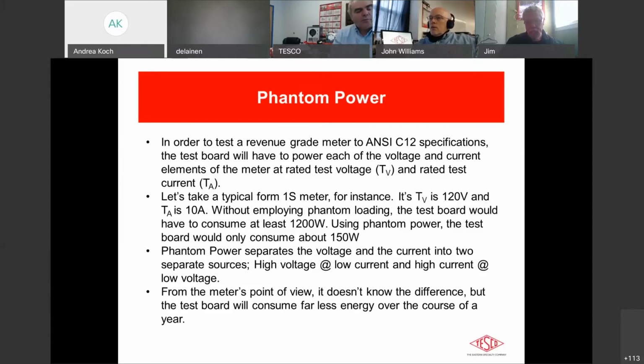When folks like TESCO create meter test boards, we create the energy that we put out to both the reference standard and to the meter in what we call phantom power. I'm sure most of you have heard the term phantom power before. What it is exactly is we're trying to create a situation whereby the meter is measuring energy as it would in the field, but in a lab situation.